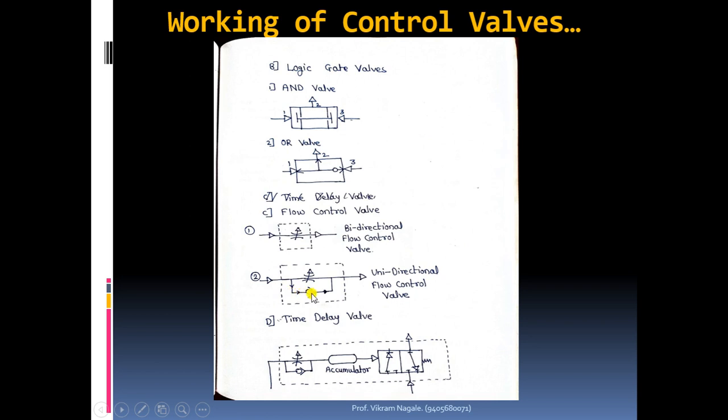So after coming into this parallel path, what will it do? Just as there is an irregularity here, there is an irregularity here too, that will cover up this opening for the parallel path, and because of this the flow will get blocked. The air has no option to flow other than to flow in the main path. Okay, means the air has no other option except to go through the main path, so it will continue flowing through the main path, and whenever we rotate the knob and control the cross section for the lining, the flow rate will change.